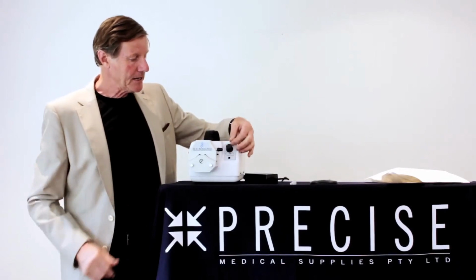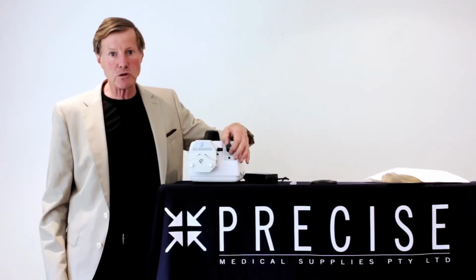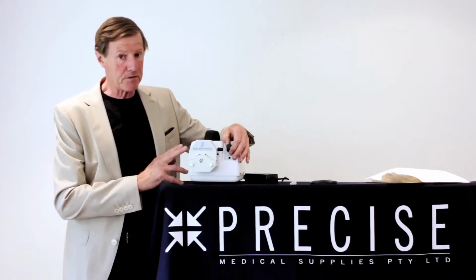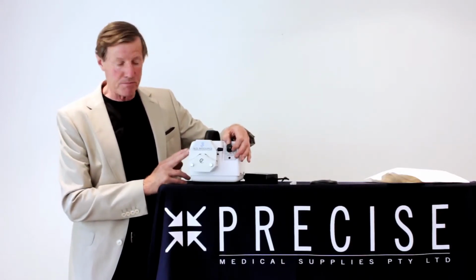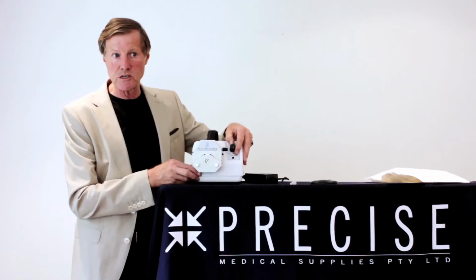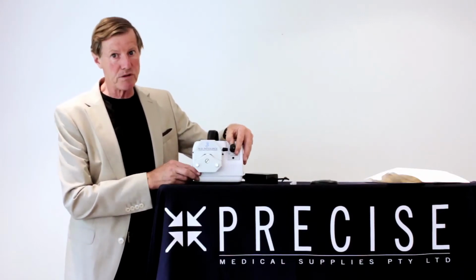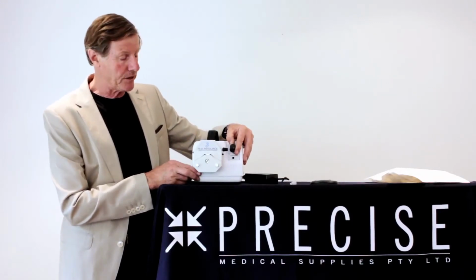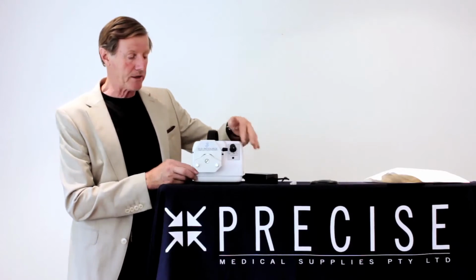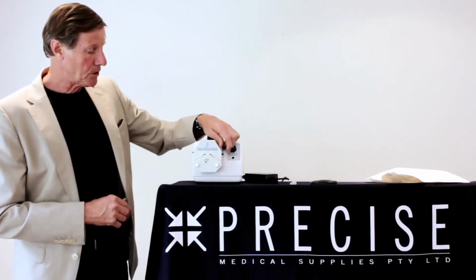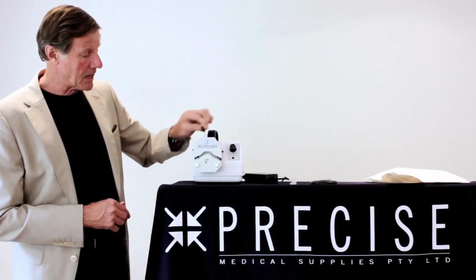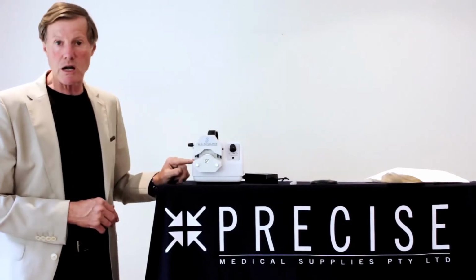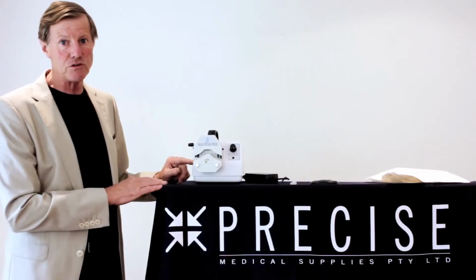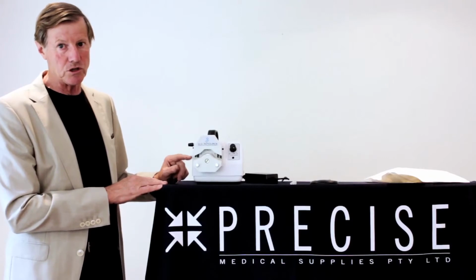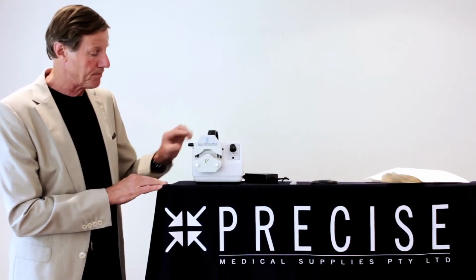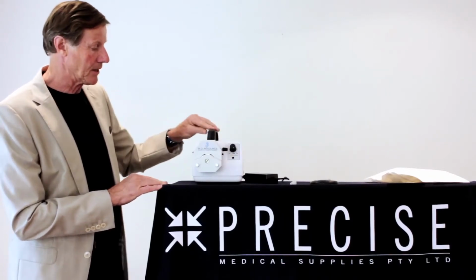On the side here, we have a control knob that controls the flow rate that will be delivered by the pump. This pump has a flow rate of 10 mils to 600 mils per minute, so it's quite a fast flow rate. And that's just controlled by that knob there. The next point to note is this clamp here, and this is where you will clamp the peristaltic infusion tubing, the single-use tubing that you will need to use with this pump. So that just clamps down like that.